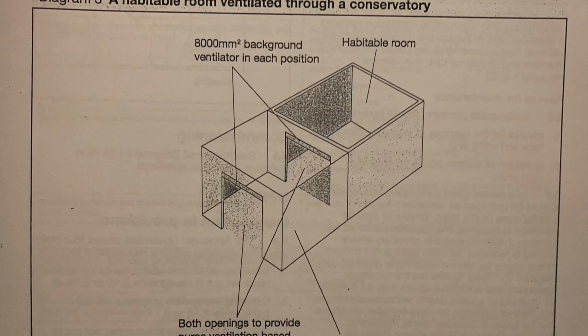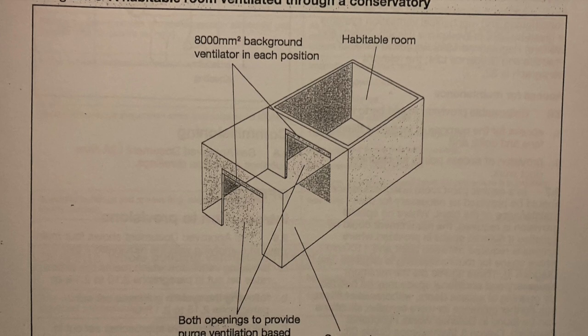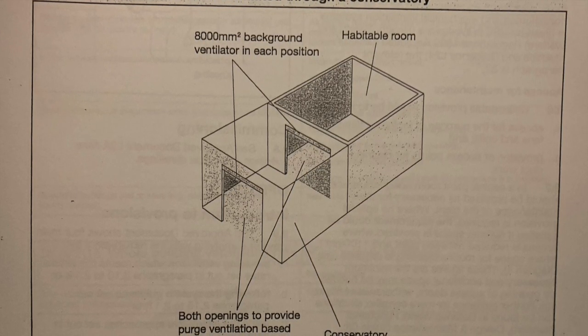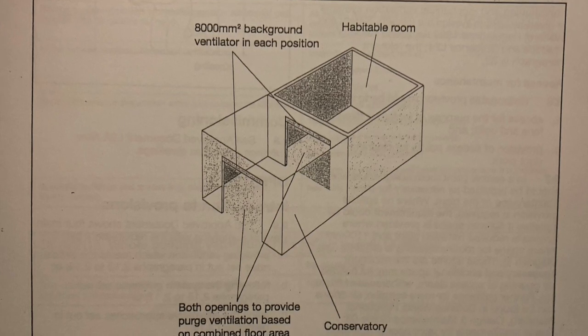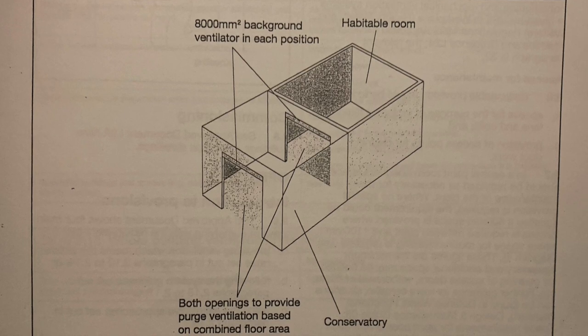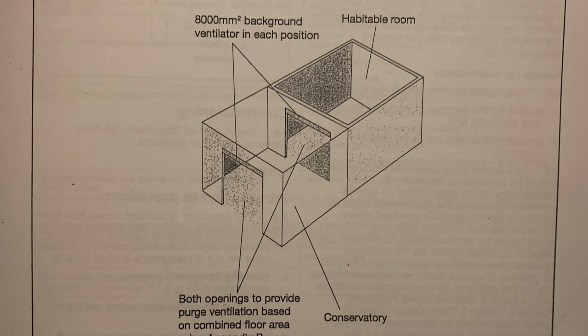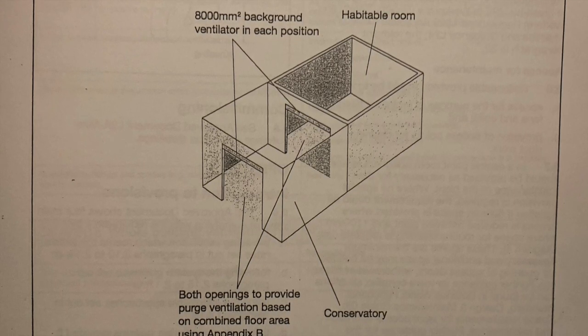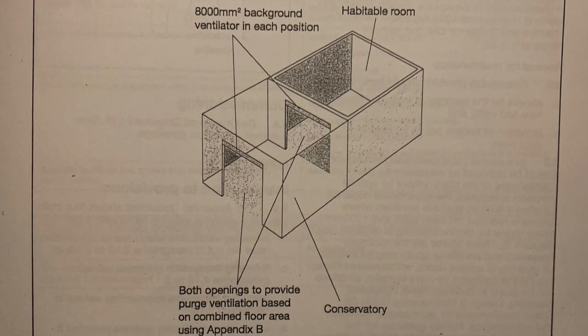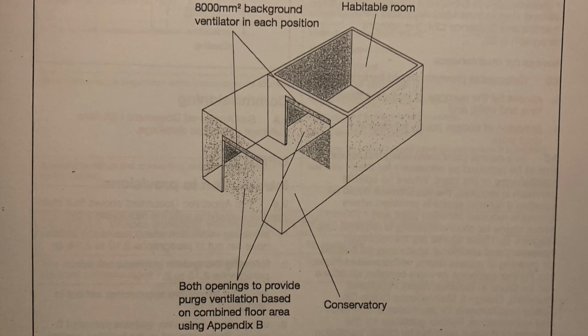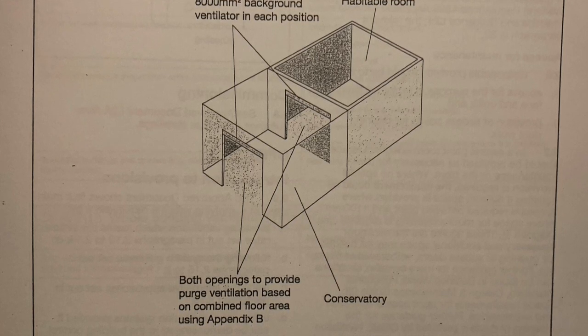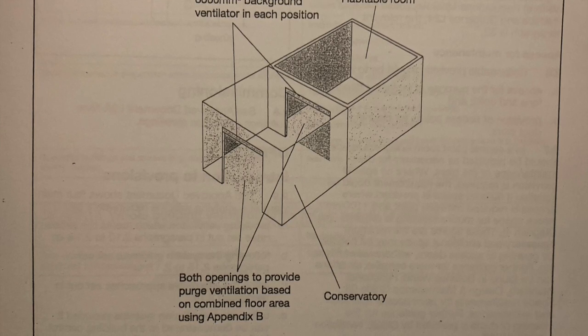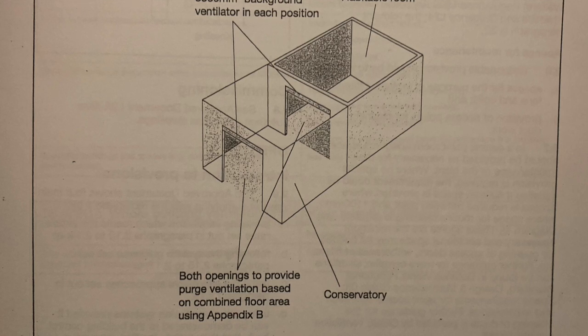The Building Regulations offer an alternative to extraction. The requirements for purge ventilation are fulfilled if: the door from the kitchen to the conservatory or extension, and the door from the conservatory or extension to outside, are each at least 1/20th of the combined floor area of the kitchen and the conservatory or extension. There must also be background ventilation of at least 8,000 millimetres squared, which must be closeable, located at least 1.7 metres above floor level, fitted to the wall between the kitchen and the conservatory, and in the wall of the conservatory to outside.